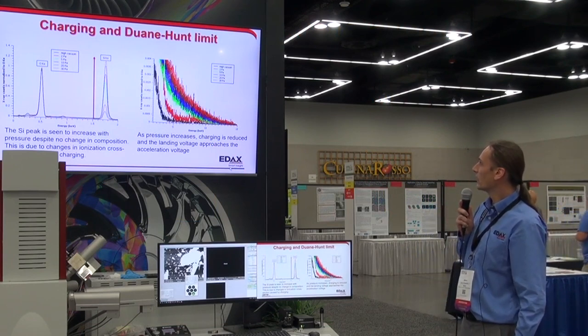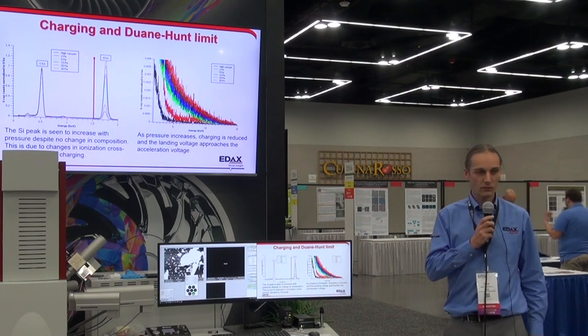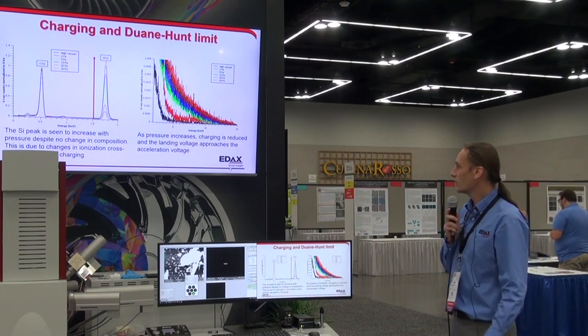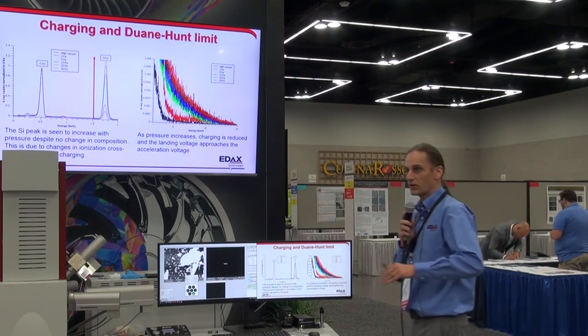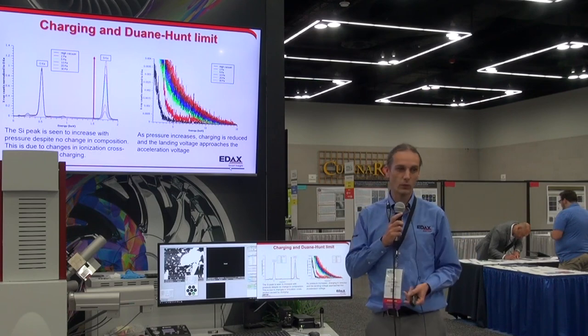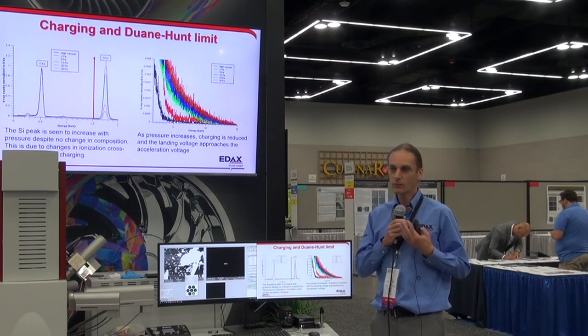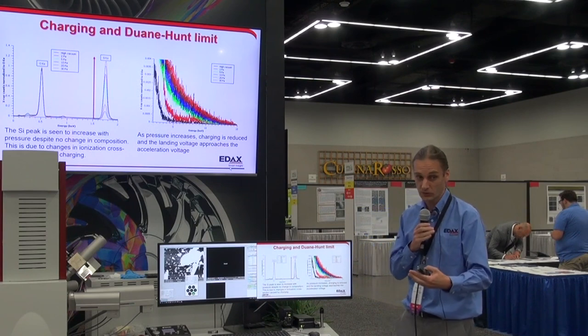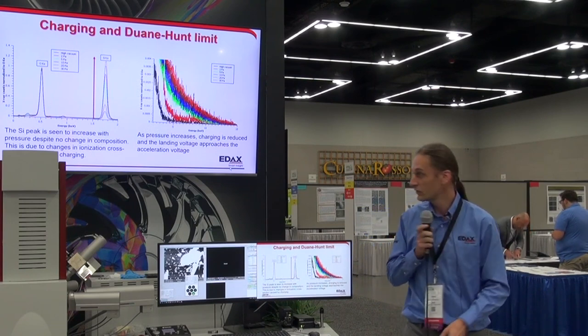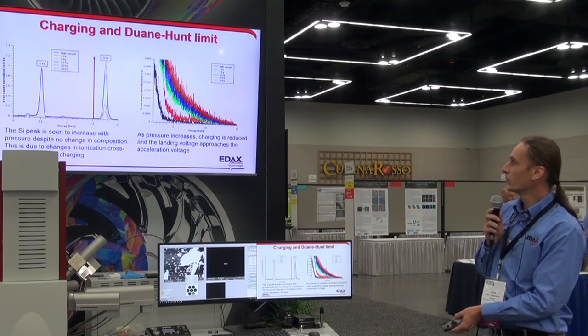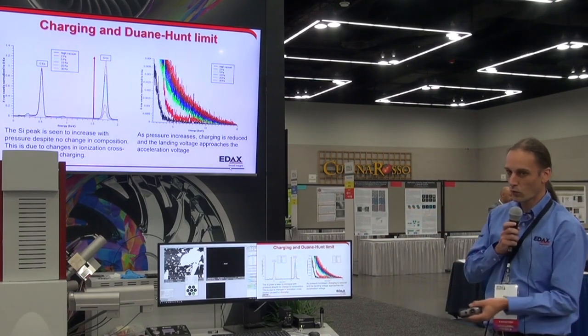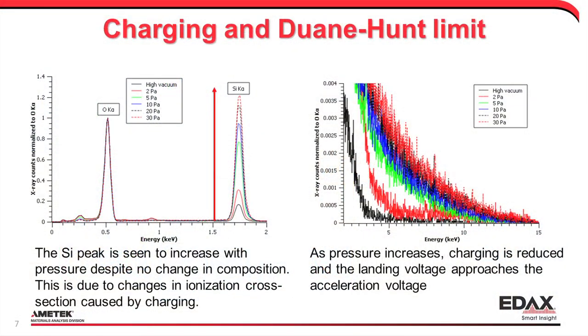At high vacuum, I'm not putting my electrons down with 15 kilovolts — I have about 3 to 4 kilovolts of landing energy. That translates into the overvoltage: we always talk about needing a certain amount of energy above the absorption line to ensure good excitation. As we decrease the pressure, we get more and more charging, less and less overvoltage, and less efficient ionization of the silicon — we get less silicon signal, even though the composition is the same.